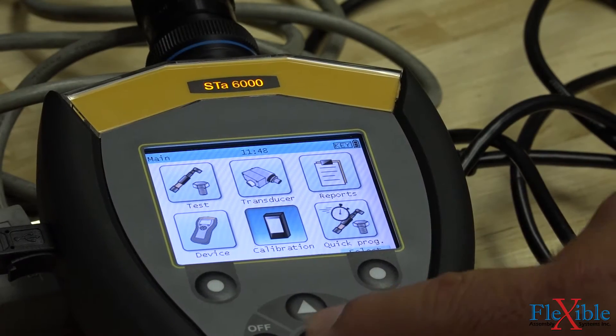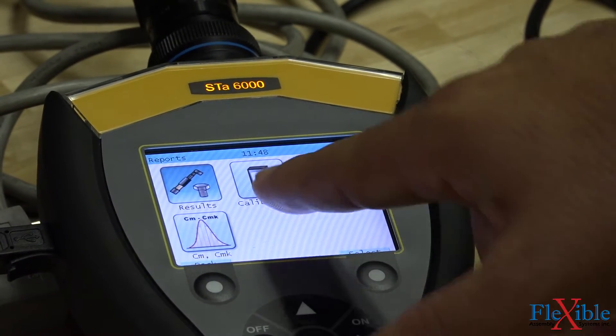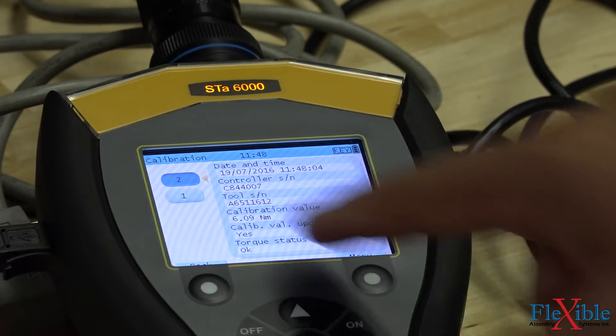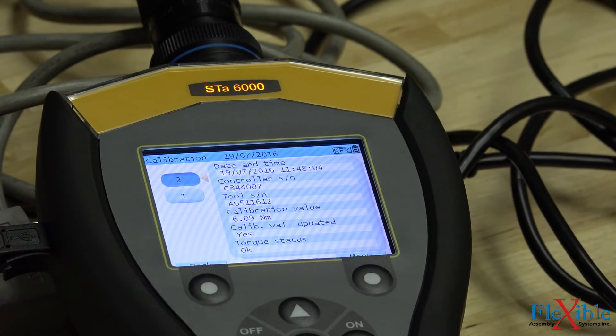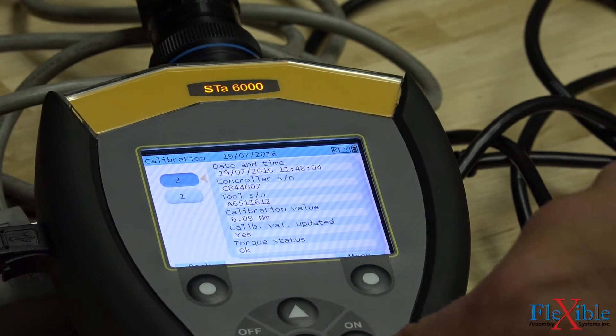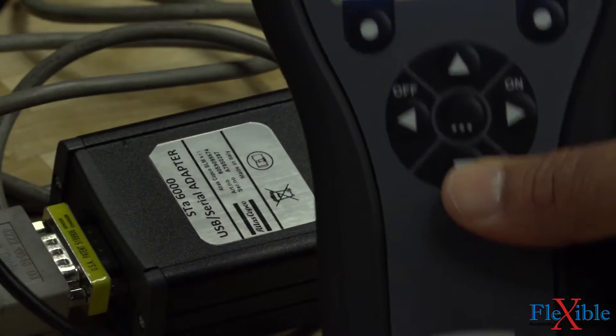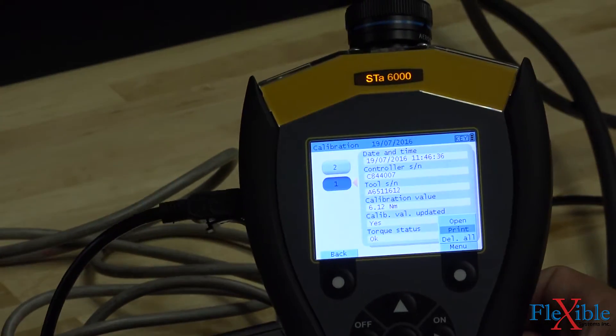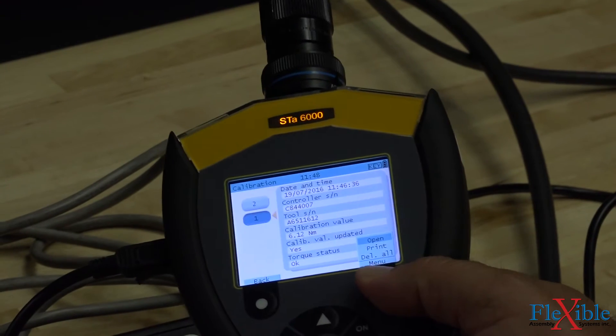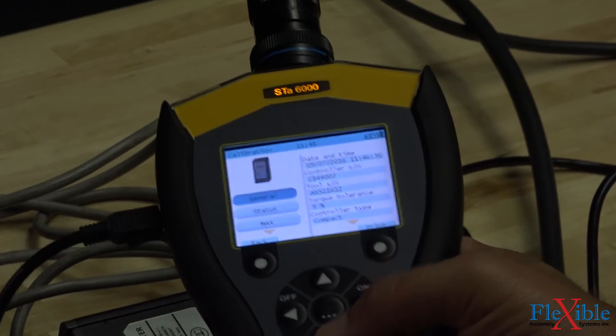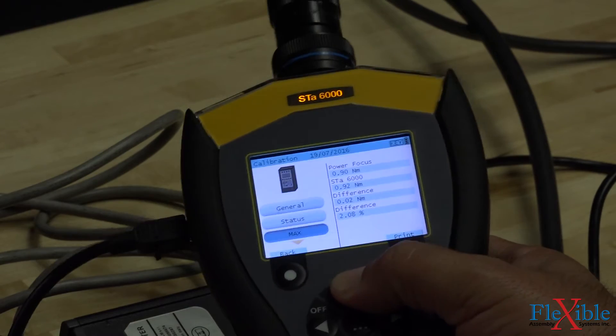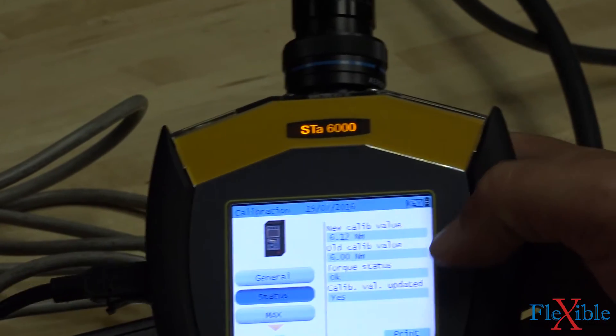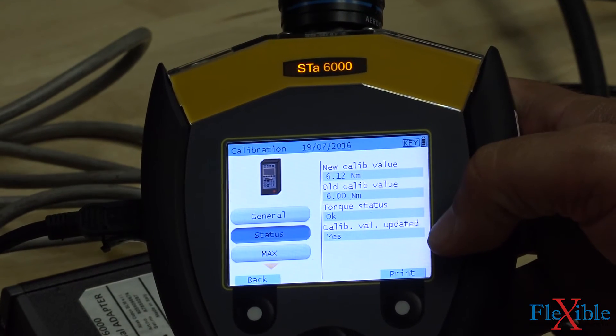Back at the main menu on the analyzer, we can go into the reports menu. Then calibration, to see the two calibrations we just performed. We can print these directly from the analyzer if it's connected to a network, delete the test, or open the report to view it. Here we see our old and new calibration values, and it says that we have updated the value.